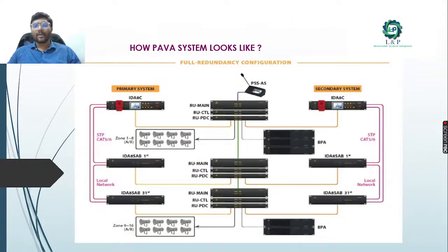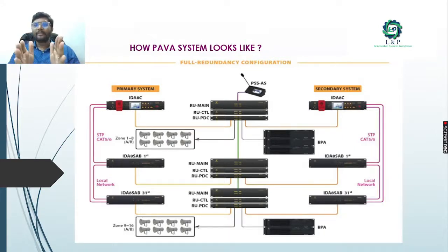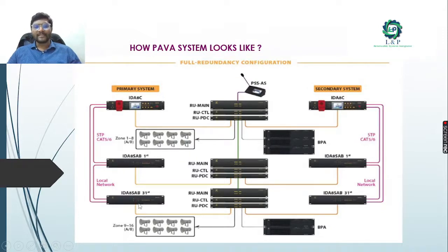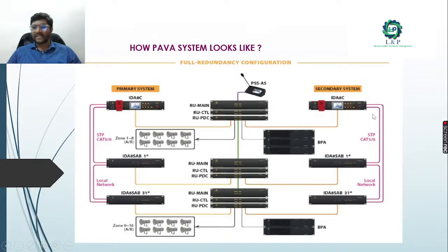Redundancy configuration is very important in modern systems. We have a main server, and from it two different systems control the entire master and slave network - a primary system and a secondary system. Both connect to the slaves through the local network and CAT6 cables. If the primary system fails, the secondary system takes charge and controls the entire building.